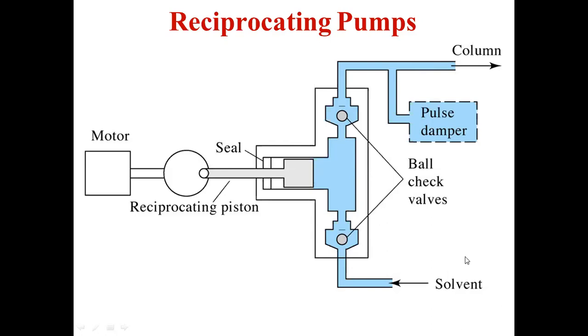Here, the solvents are going to be mixed. If you are going to use different solvents of different composition, they are mixed prior to their movement towards the pump. So the solvent in different composition, or constant composition, or a single solvent, is made to move towards the column by means of a reciprocating pump. The movement of the solvent can be seen by means of check valves.